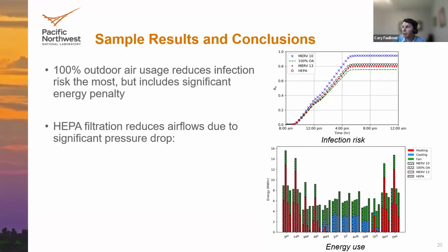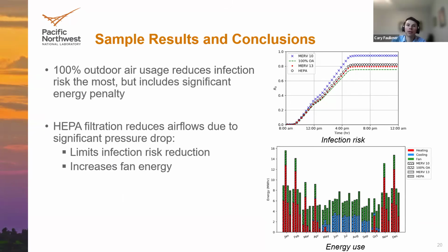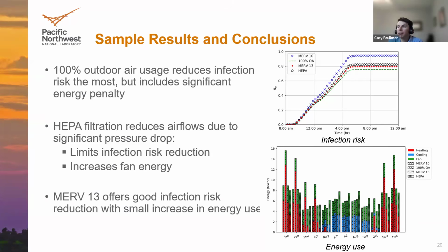And then the HEPA filtration, while these HEPA filters are the most efficient in terms of capturing small particles, they can impose a significant pressure drop on the system. For our simulation setup, we did find that the significant pressure drop from the HEPA filter had a negative impact on the HVAC system operation, in particular, large increases in fan power and reduced airflow rates, which led to limited infection risk reduction because of those reduced airflow rates. Even though it was doing a good job capturing the particles, it just wasn't pushing enough air through to the zones. And then we found that MERV 13 offered a good balance between infection risk reduction, maybe not as low as 100% outdoor air but just above that, with a pretty small impact on energy use, as these filters impose some pressure drop on the system, but not nearly as significant as the HEPA filters.